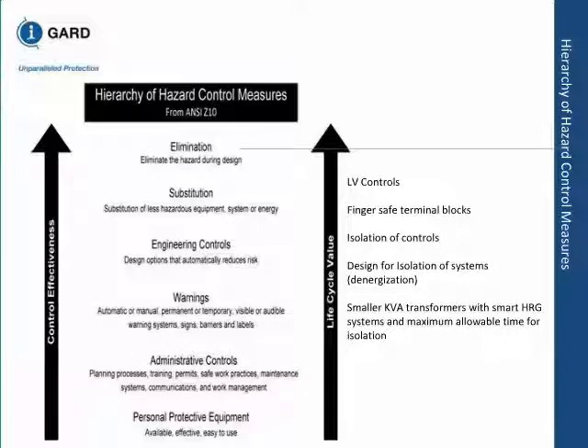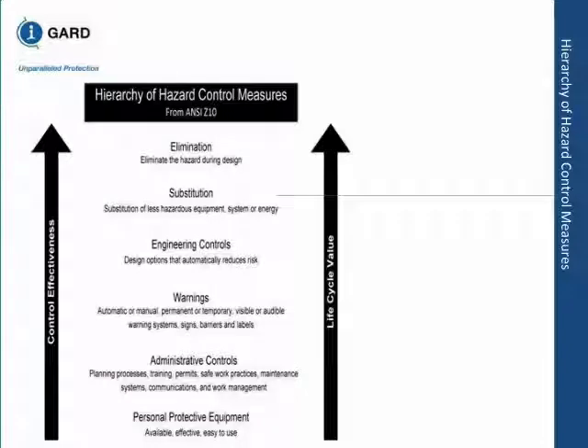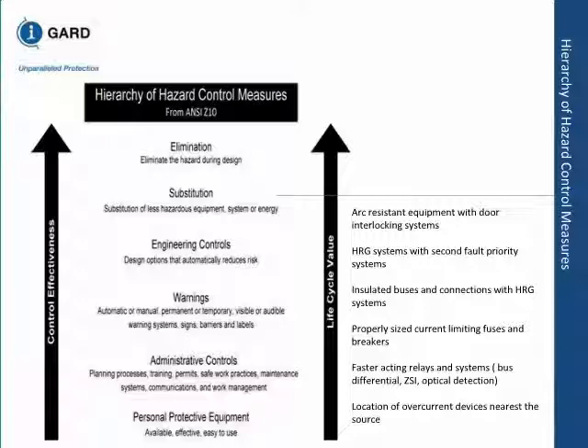Okay? Next, look at substitution. You can use arc-resistant equipment with a door interlocking feature. That means it doesn't operate till the doors are interlocked. You can use a high-resistance grounding system and give it second fault priority. With a high-resistance grounding system, the first fault would not cause any problem, but if a second fault happens, you may have a flash, so you can have a second fault priority system.